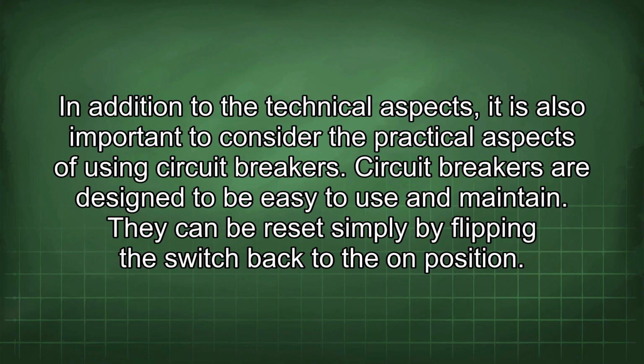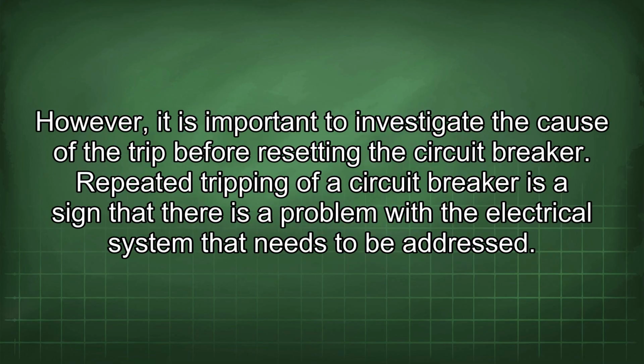In addition to the technical aspects, it is also important to consider the practical aspects of using circuit breakers. Circuit breakers are designed to be easy to use and maintain. They can be reset simply by flipping the switch back to the on position. However, it is important to investigate the cause of the trip before resetting the circuit breaker. Repeated tripping of a circuit breaker is a sign that there is a problem with the electrical system that needs to be addressed.